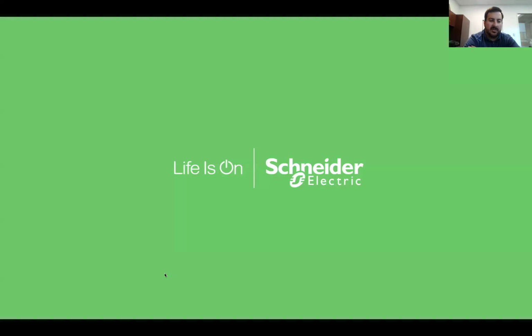A battery energy storage system, although it's very similar, the basic components of it being an inverter, batteries, and a charge controller. The chemistries of the batteries are different. The design of the inverter and the way it handles heat dissipation and things like that are different. And it's designed more for a long-term power supply. And there are differences in the way those UPSs versus battery energy storage systems are constructed, where a battery energy storage system is meant to provide long-term power in the world of hours instead of minutes, which is what you would expect from a UPS.